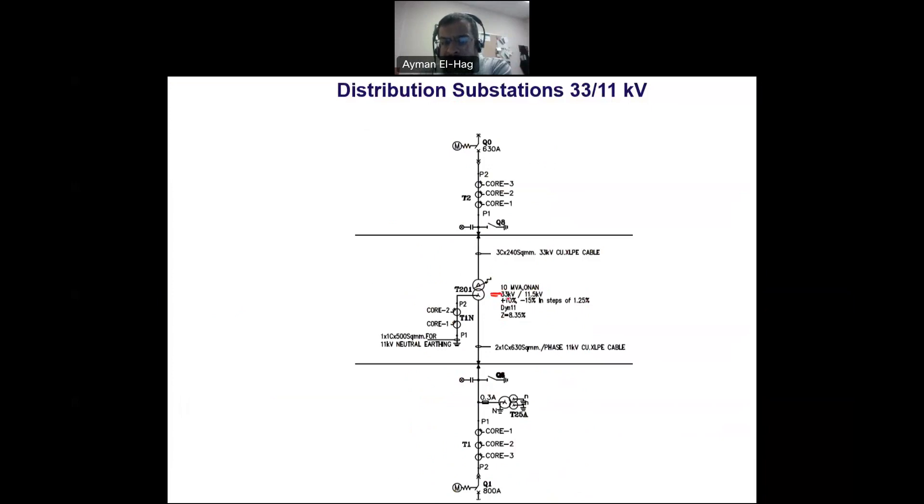Then we have the voltage level, 33 kilovolt by 11.5 kV. This is when the transformer is at no load. Then we have plus 10% to minus 15% in steps of 1.25%. To control the voltage at the secondary side of the transformer, we need this because the load is varying. As the load goes up and down, the voltage will go up and down.